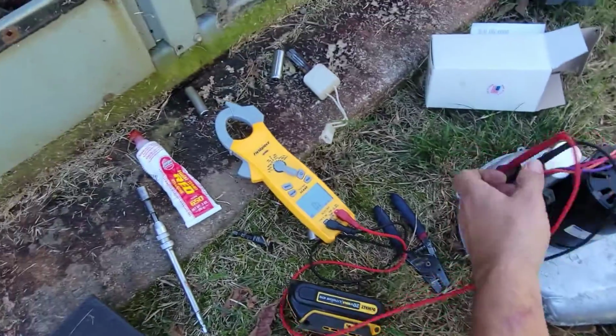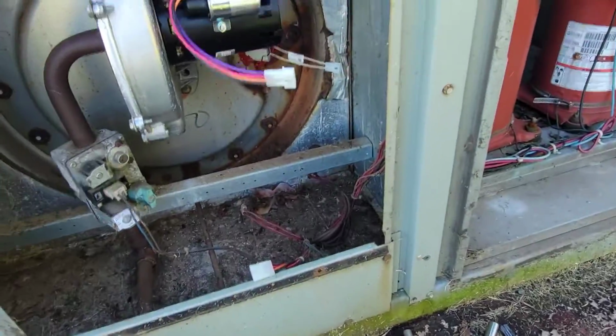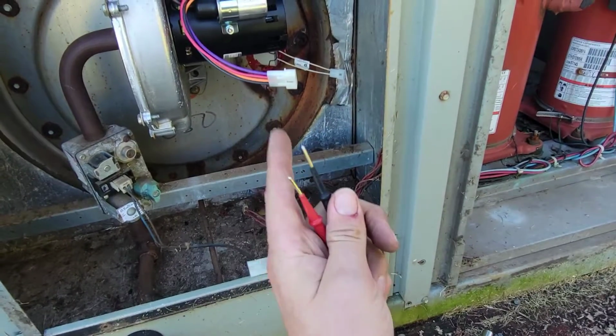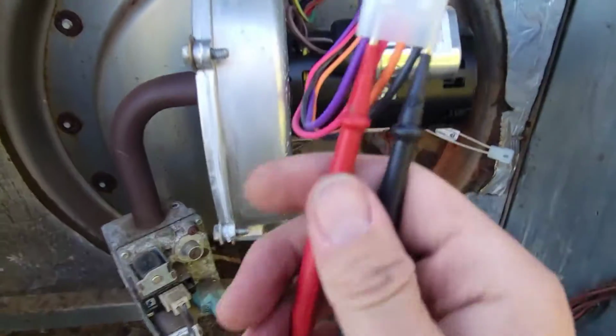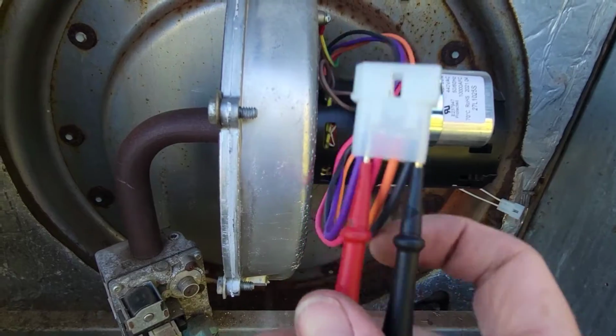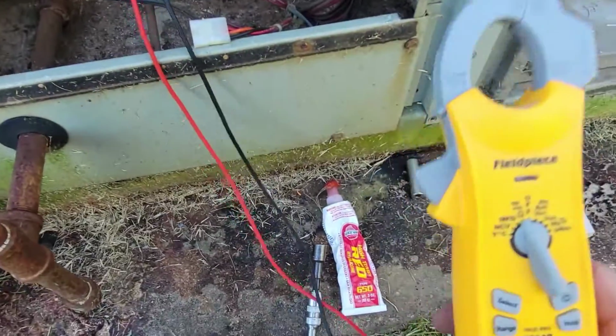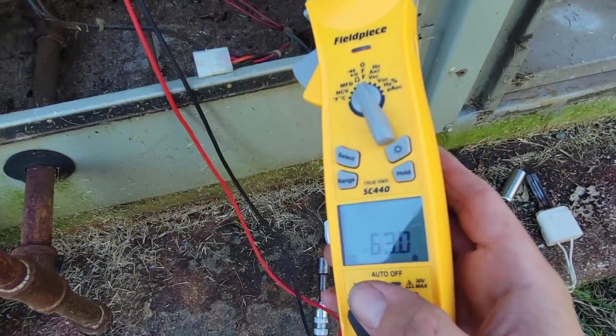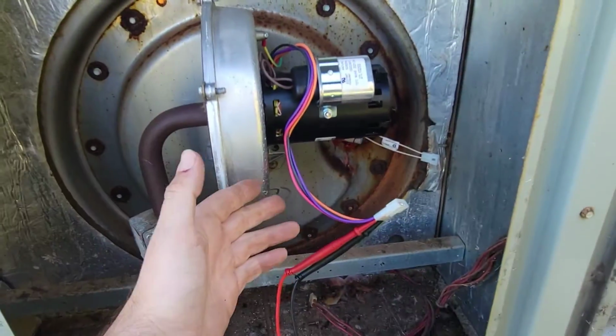So now I'm going to show you the new motor, and we're going to measure the resistance for the windings of the new motor. All right, new motor line, which is purple and black, meter on ohms, 63. So we're measuring resistance. This motor's good.